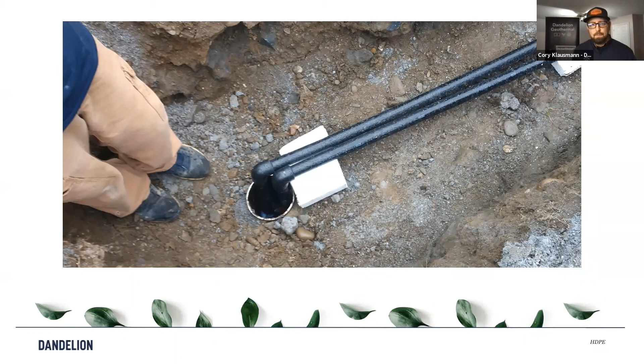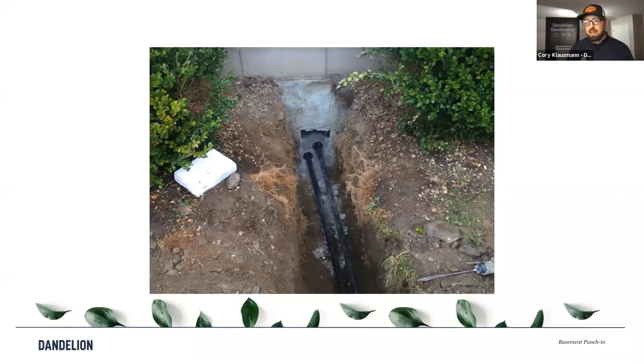This is what it looks like going into the basement. We basically cut a hole into the foundation, seal it up and reinforce it. We'll pressurize the geothermal ground loop, which is made out of 78% water and 22% propylene glycol, and leave it pressurized for a period of time. Once we've confirmed the integrity of that line is true, we'll bury the line and bring the house back to rough grade. Next slide, please.